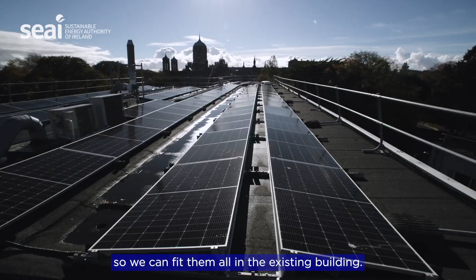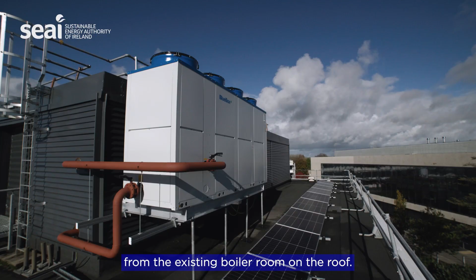The main construction challenge with an existing building is space. We had to make sure there was enough room for the large air-to-water heat pump, buffer vessels, pumps, and enough roof space for PV panels to fit them all into the existing building. We cantilevered the heat pump from the existing boiler room on the roof, outdoors where it needs to be, and it's been very successful.